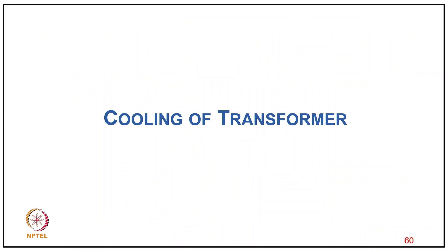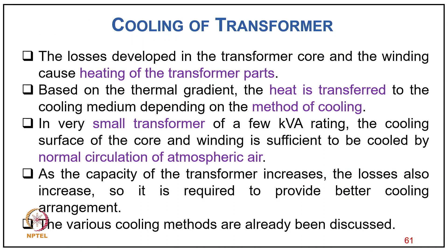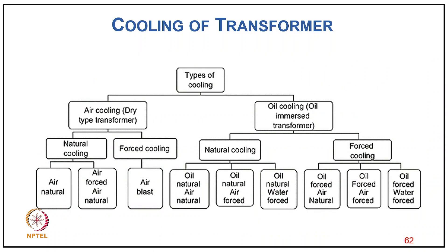Coming to the cooling of the transformer: losses developed in the transformer core and windings cause heating. Based on the thermal gradient, heat is transferred to the cooling medium. For very small transformers up to about 3 kVA rating, the cooling surface of the core and winding is sufficient for natural air circulation. As transformer capacity increases, the losses also increase, requiring better cooling arrangements.